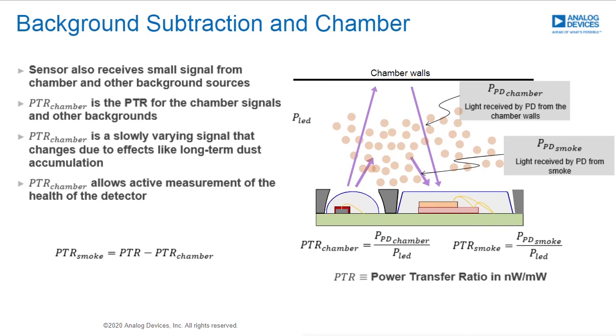So your chamber is going to give you some initial background response at time zero, let's say, when the smoke detector is first turned on. And then over time, you may get some slowly varying signal changes in that background response due to long-term dust accumulation. It could be some type of grime or soot from previous smoke events that build up just over time with a smoke detector being on your ceiling for 5 to 10 years. So in the background, there would need to be some algorithm that helps to eliminate this background response. And it's really a simple kind of long-term high-pass filter that can filter this signal out.